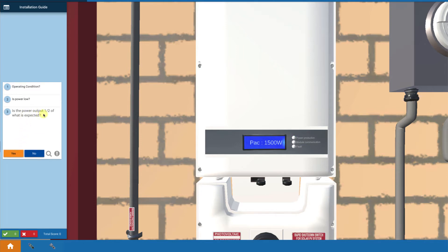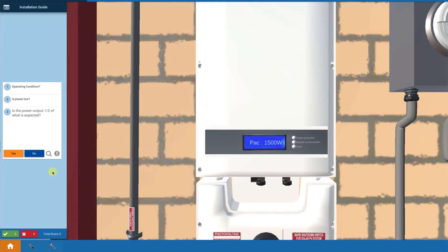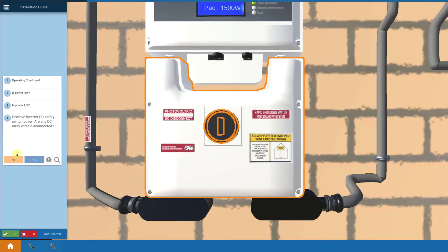Now, is the power one-half of what's expected? The answer is yes, so our suspicions are raised. If we've got one-half power and we have two strings, we highly suspect that one of the strings is okay, but one of the strings has a problem. We have an issue with half power.